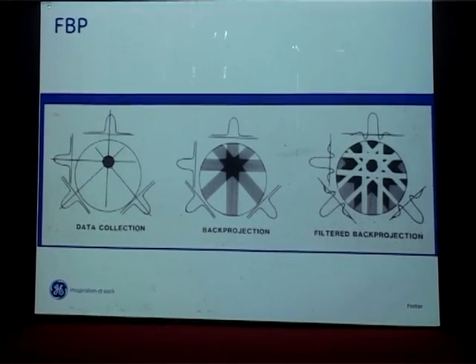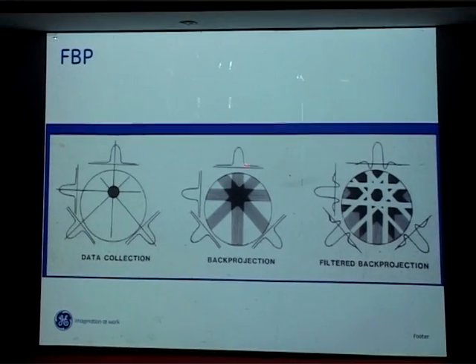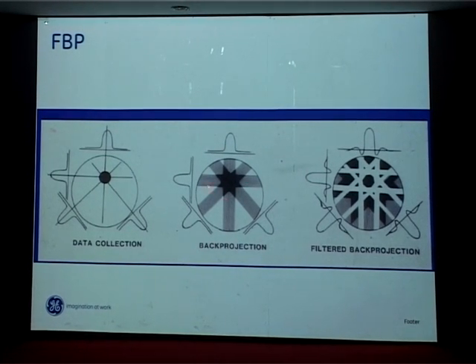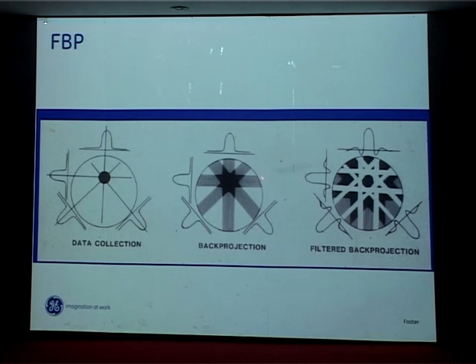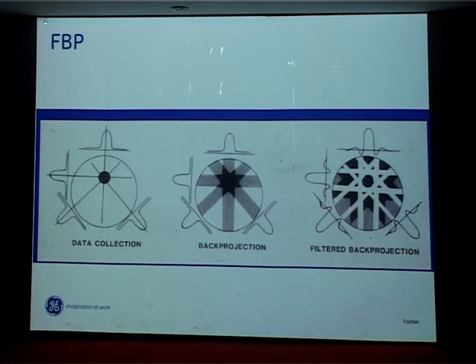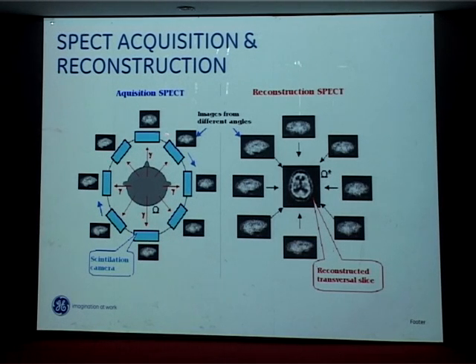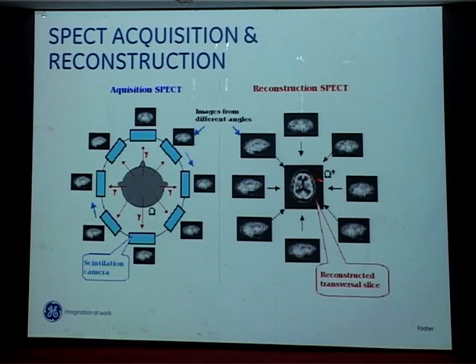Image reconstruction shows how activity is distributed in a particular organ. Simple back projection gives a distribution but produces a star artifact that degrades the image. That is why filtered back projection is used — applying a filter to cut out the noise and obtain a better image of the activity distribution. The camera rotates at various angles over the patient and the image is reconstructed; this example shows a brain image.